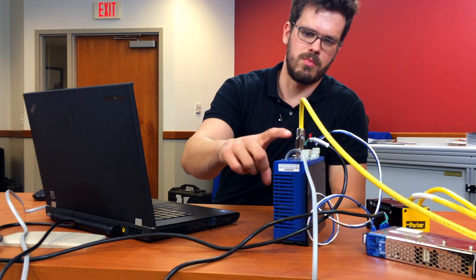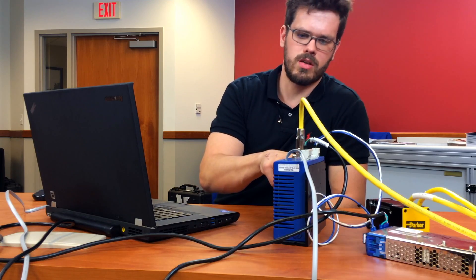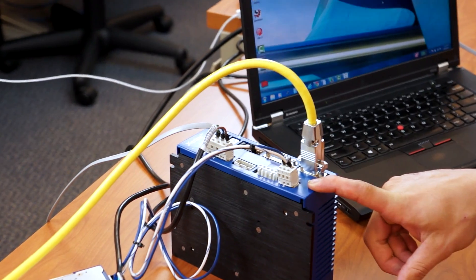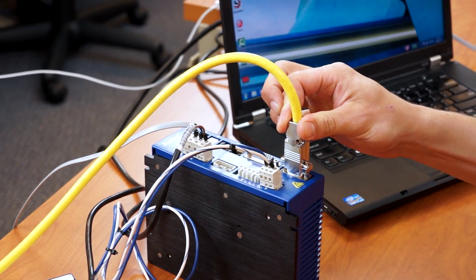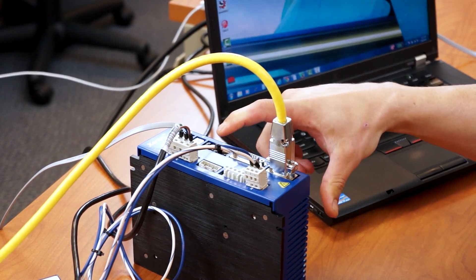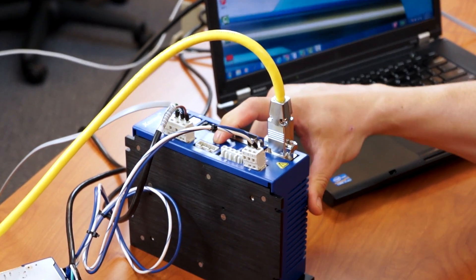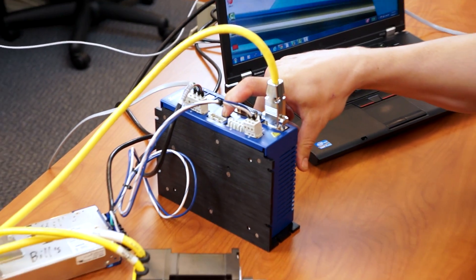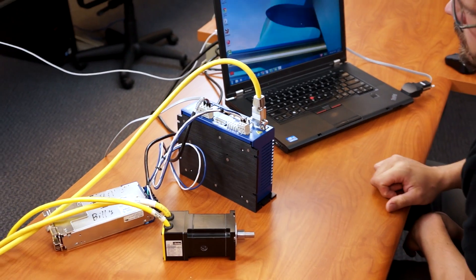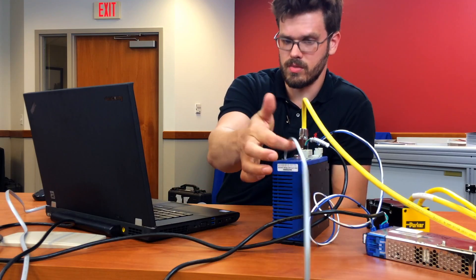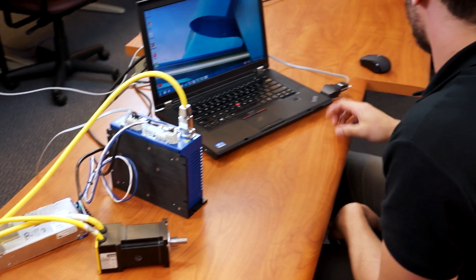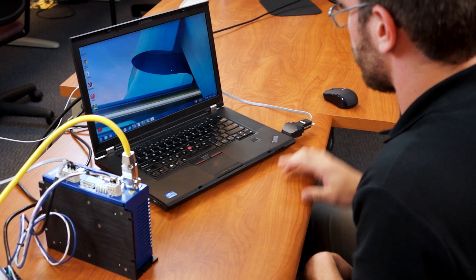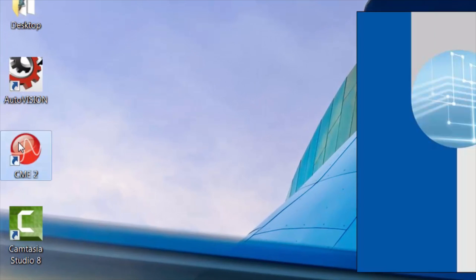To start with, I have my main and logic power hooked up to the amplifier, as well as the feedback connector from the motor. But for now, I'm not going to plug in the motor power until I have the parameters loaded onto the drive. I then hook up the serial connection to my USB to serial converter and open up CME2.